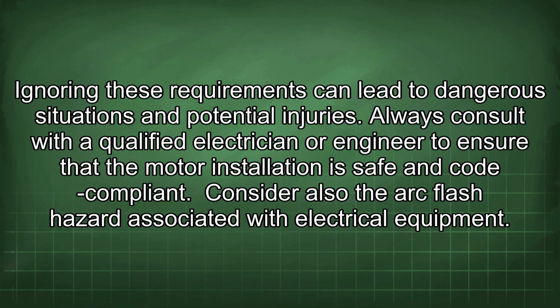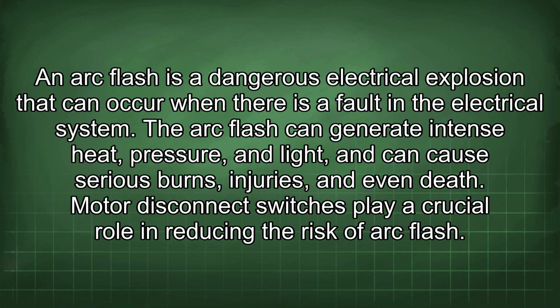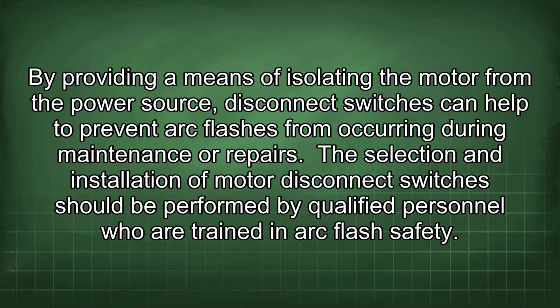Consider also the arc flash hazard associated with electrical equipment. An arc flash is a dangerous electrical explosion that can occur when there is a fault in the electrical system. The arc flash can generate intense heat, pressure, and light, and can cause serious burns, injuries, and even death. Motor disconnect switches play a crucial role in reducing the risk of arc flash. By providing a means of isolating the motor from the power source, disconnect switches can help to prevent arc flashes from occurring during maintenance or repairs.